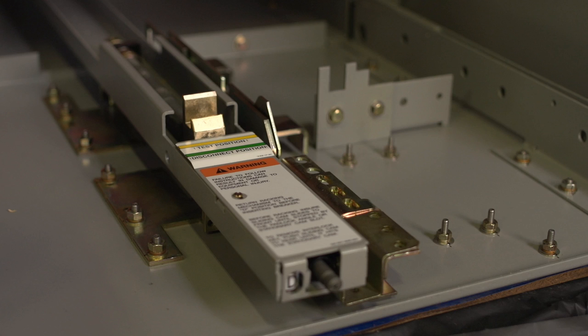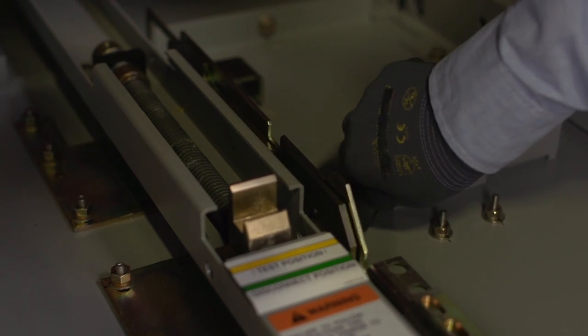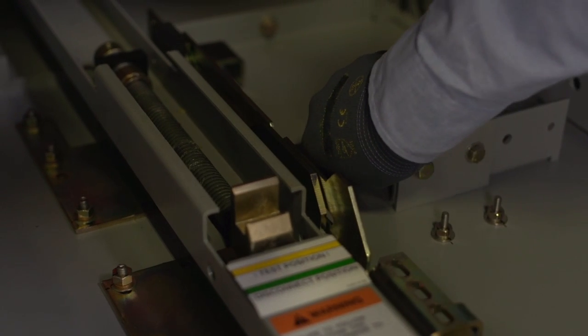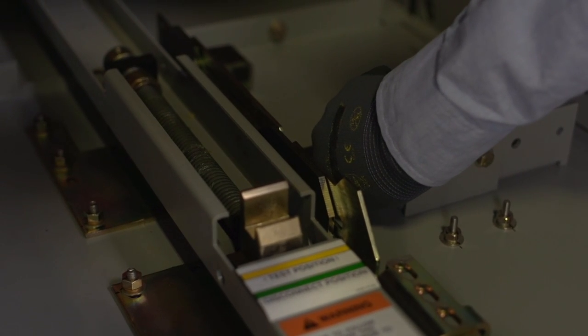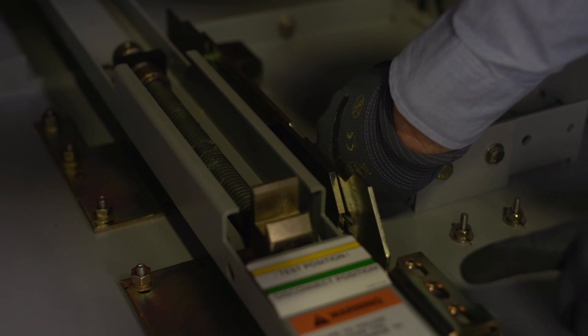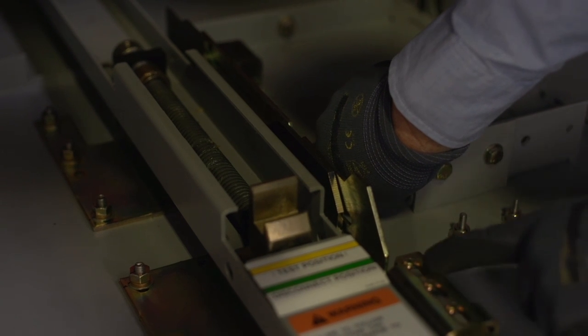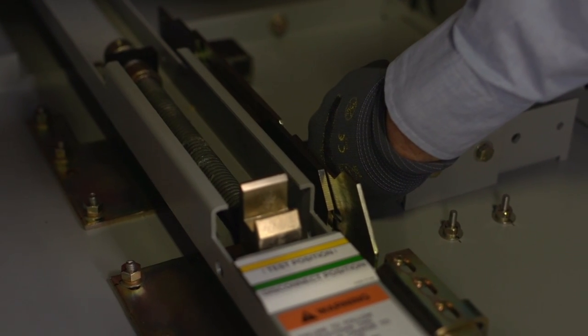In order to see if these line up properly, you must look straight down from the top of the circuit breaker. Next to the racking mechanism is a sliding cam plate. It has a padlock provision, so up to three padlocks can be installed to prevent closing of the circuit breaker.